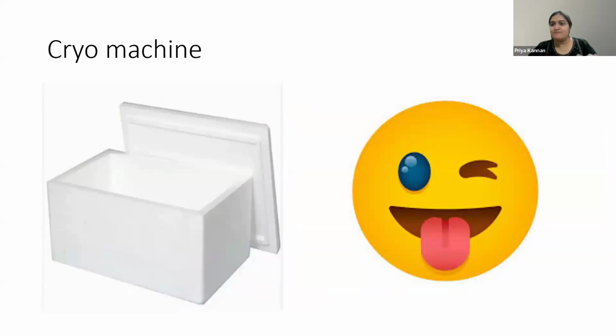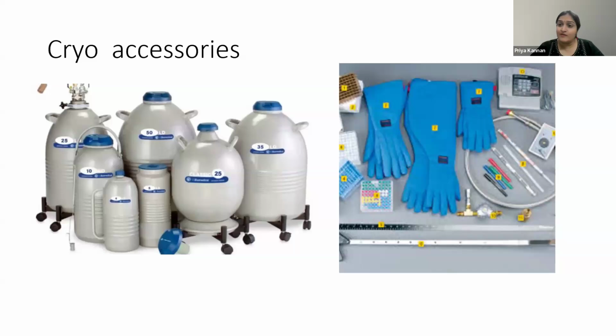But this being the crux of the cryo machine that we are using now, you need some accessories to go along with it. Without that, your cryo is not complete at all. One is the cryo tanks. When you're having cryo tanks, you need 3 types. You have to separate your sperms, your semen samples, and your embryos. You cannot have both in the same cryo tank. So you will have to have 2, and immediately the minimum is 2 cryo tanks for you. You need one more cryo tank, exclusively for storage of liquid nitrogen, for you to keep refilling the cryo tanks again and again.